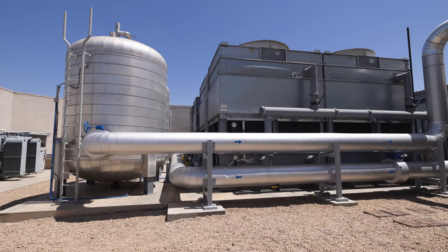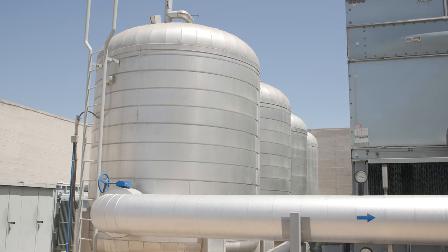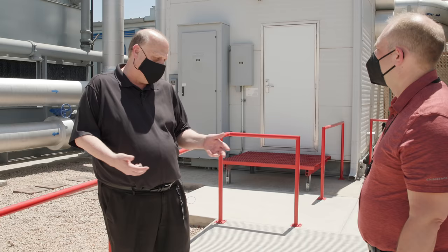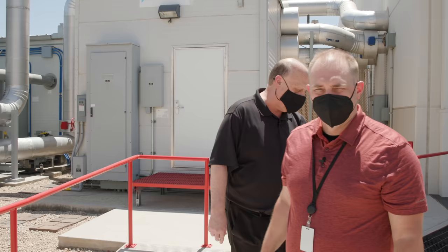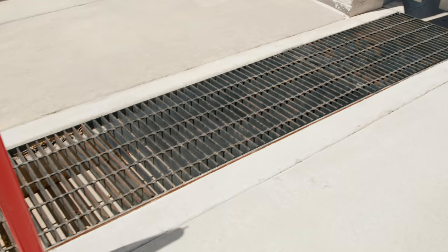We also have a thermal storage tank — 8,500 gallons per chiller — which keeps the water chilled for about 20 to 25 minutes for ride-through in the event of an issue. We get about seven inches of rain a year and do have a monsoon season. The soil doesn't hold water so it just runs off. The facility is on an incline away from the building, with water grates to drain water away from the facility at all times.